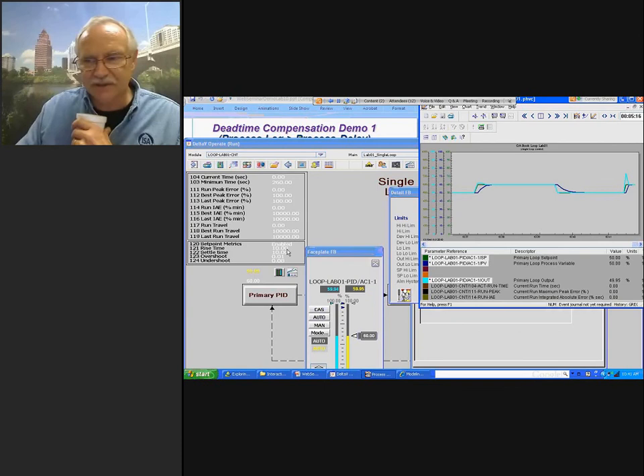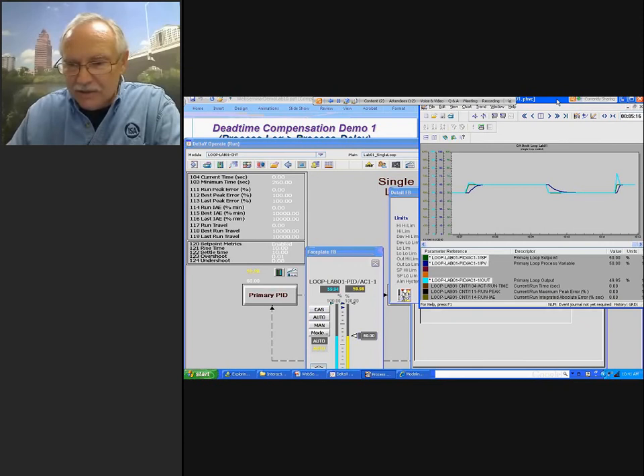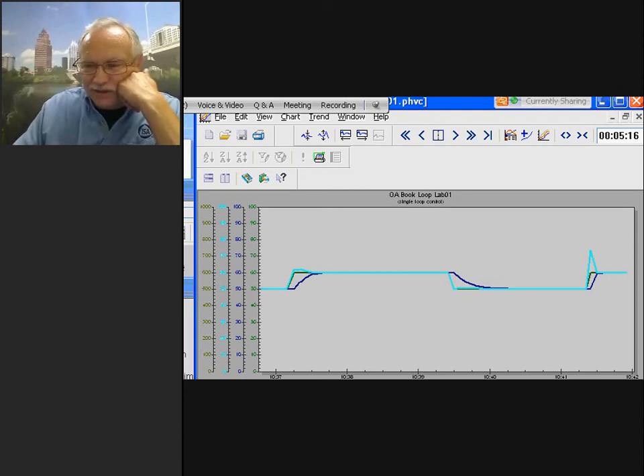We have a tiny, well, this is negligible. I mean, you've got noise only in there larger than that. So the overshoot and undershoot really is not significant. And if we zoom in on this, we can see, boy, that looks like a pretty darn good response.